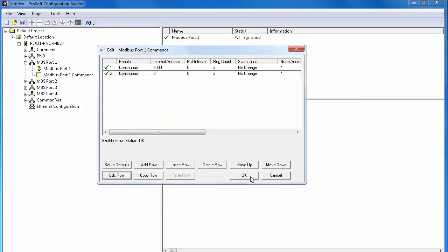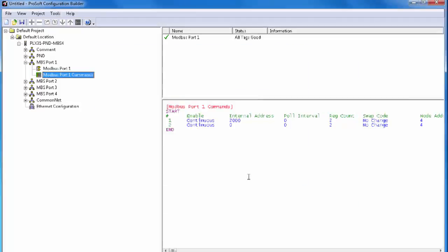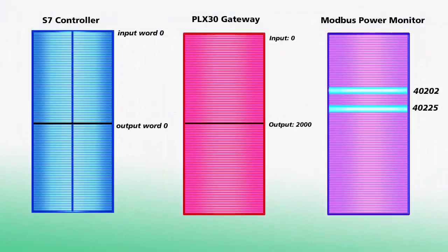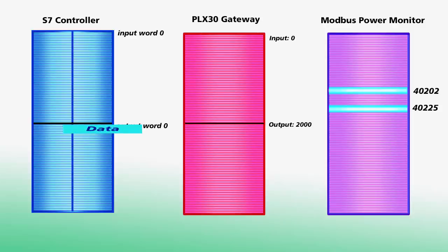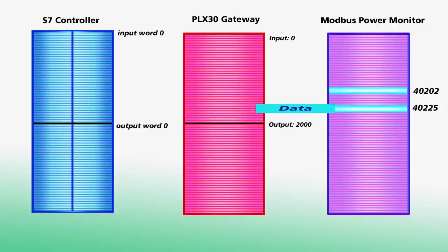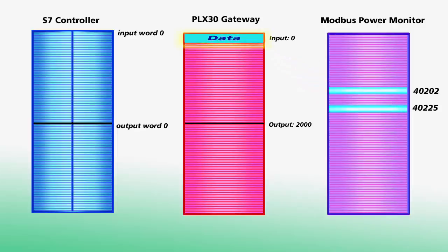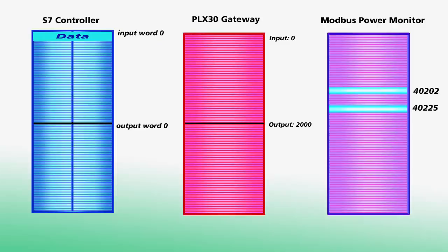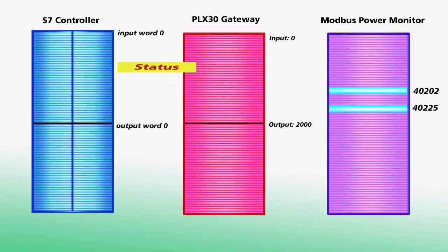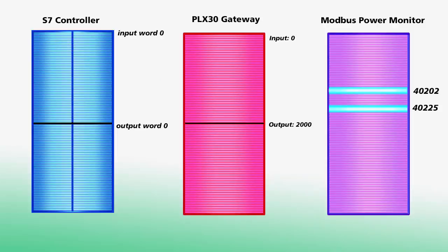What all this means is that with our write command, we'll be taking 32 bits of data starting at output word 0 of our S7 controller. Moving it into address 2000 of our internal database. And then pushing it into address 40202 of our power monitor. We'll be reading the data at address 40225 of the power monitor. And we'll bring it into address 0 in the gateways database, where it can then be read into input word 0 of the S7 watch table. Our status data will be at internal address 1250 and can be read into the S7 input data as well.